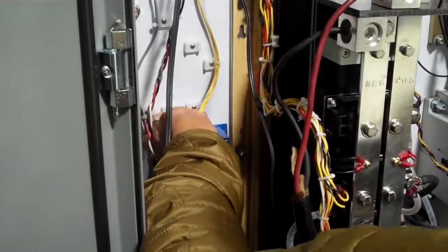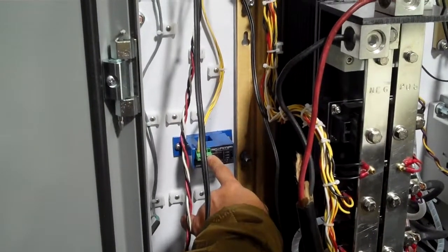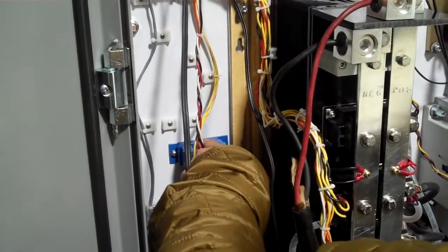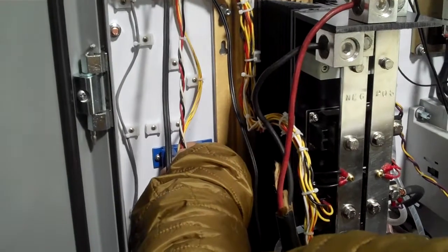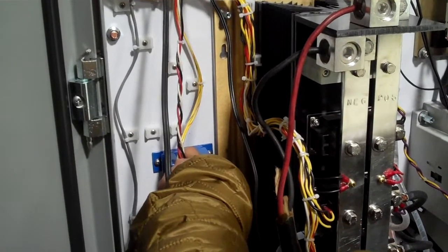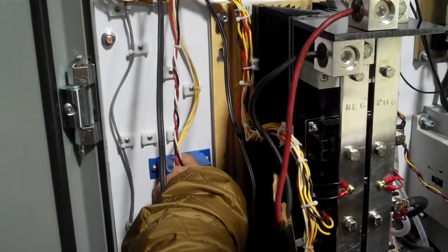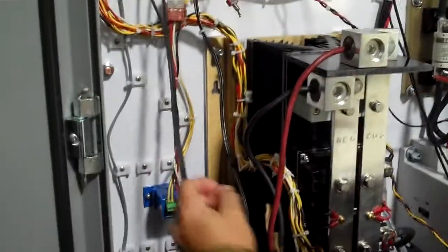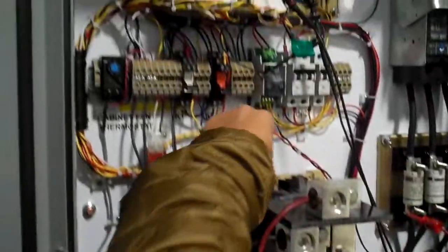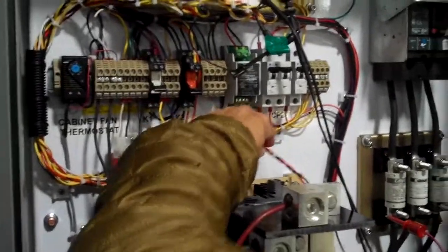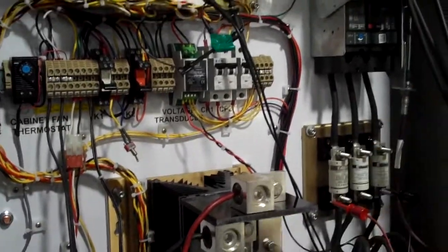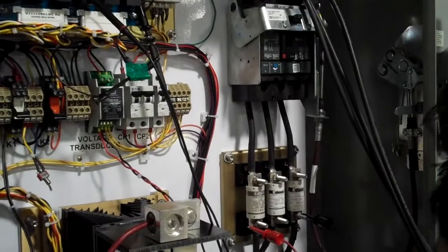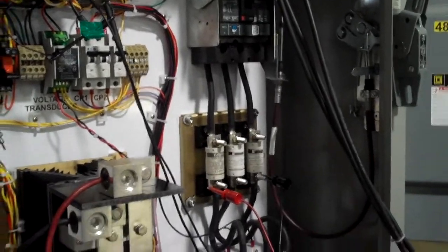We have power, and we're not picking up any output on this particular test. We will have our connector wire going from the negative bus through here to our load to monitor our current. And that's basically it. We have our breaker, we have our fuses. So in this part of the video, we're going to go ahead and get started by applying 120 volts.